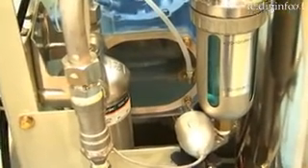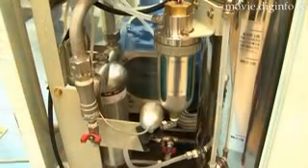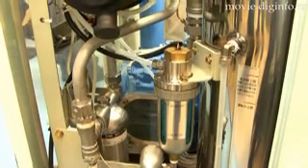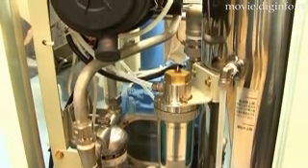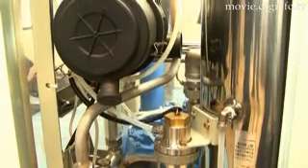The i14000 air compressor series employs an oil-free, environmentally friendly water lubrication system that achieves a high degree of efficiency through the use of water seals. The compressors in this series feature direct-drive coupling of the compressor and the IPM motor, which eliminates kinetic loss while boosting motor efficiency by up to 8%.